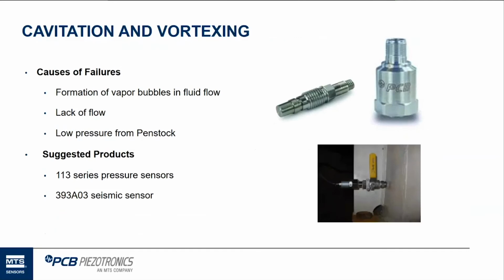And then cavitation and vortexing issues. So this happens a lot in the penstock at the lower end, near where the water enters into the turbine chamber. Sometimes you'll get vapor bubbles in the fluid flow, and this is caused by possibly the water flow. I'm not an expert in water hydraulics as far as that goes, but I've seen this happen where there's vapor bubbles in the fluid flow, which causes cavitation. Lack of flow and low pressure both can cause vortexing within this chamber. So, we've got some seismic sensors that can detect this, along with some pressure sensors, real standard, pretty low cost pressure sensors that can look for these types of problems within the penstock.